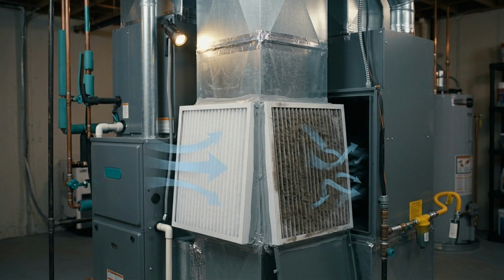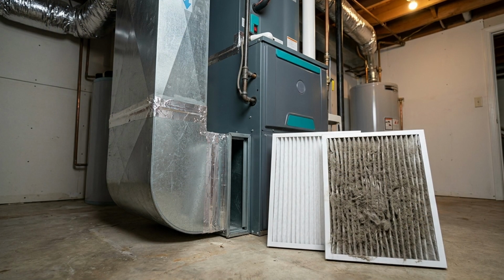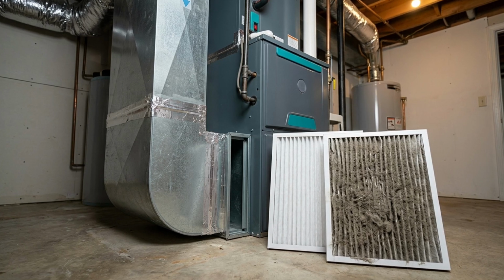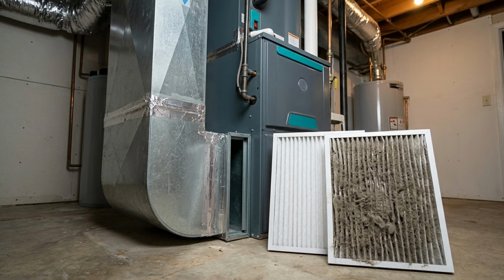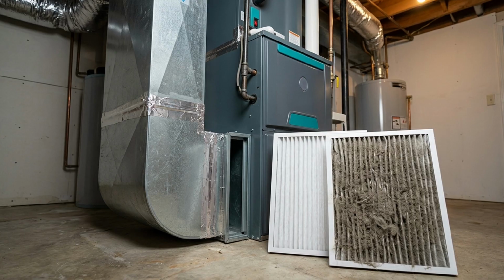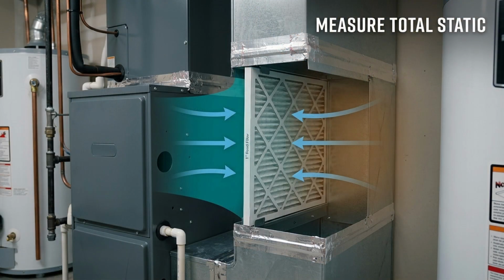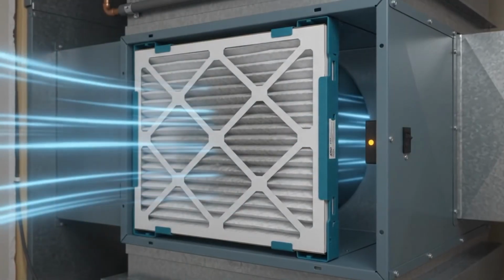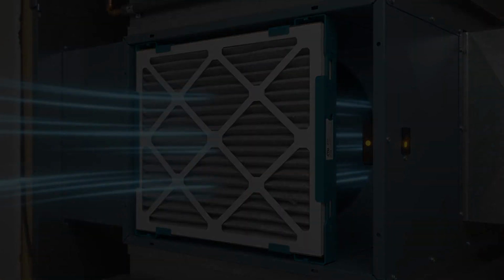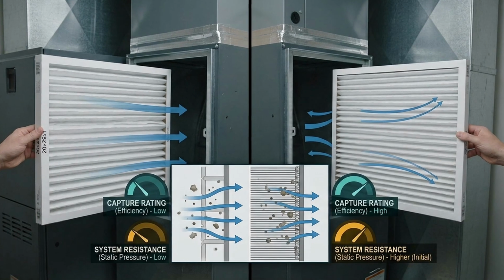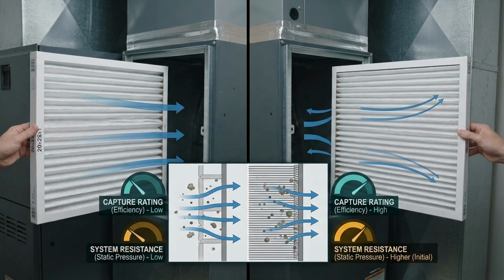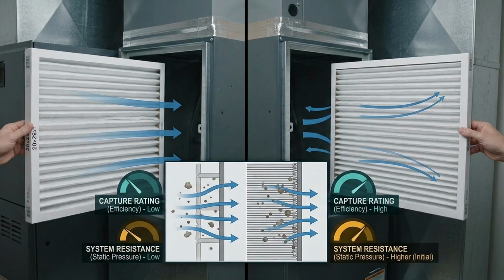The useful comparison is not MERV number against MERV number. It is capture performance, published pressure drop information at the relevant airflow, physical size, and system compatibility. Condition changes the comparison again. The resistance of a new filter is its initial pressure drop. As a filter collects particles, its resistance can increase.